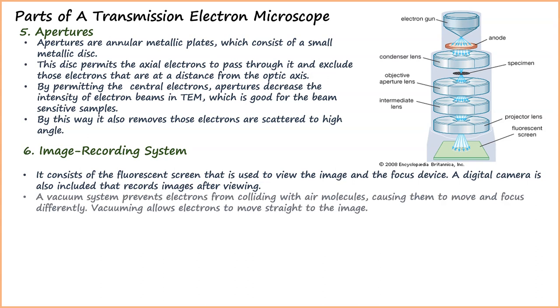A vacuum system prevents electrons from colliding with air molecules, causing them to move and focus differently. Vacuuming allows electrons to move straight to the image. The vacuum system consists of a pump and gauge, valves, and a power supply.